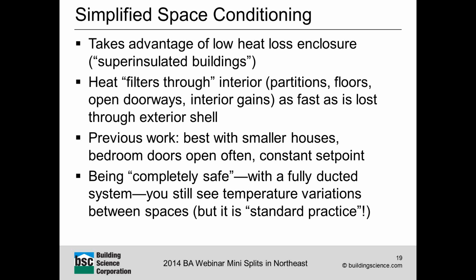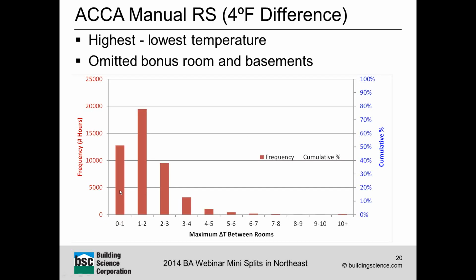So, we did a similar type of analysis using ACCA Manual RS, looking at the 4-degree temperature difference. We just did a simplified analysis here. We took the highest and lowest temperature in the house at the various points that we measured, took the difference between those 2 points, and plotted how many hours there were at those various temperatures, and just added up the number of hours. So you can see that there were a fair number of hours with a 0 to 1 degree temperature difference between our various measurements. The majority was in the 1 to 2 degree range, then 2 to 3, and it kind of tails off from there.